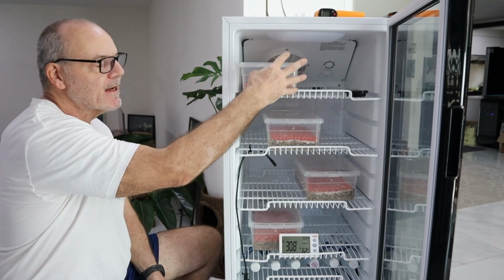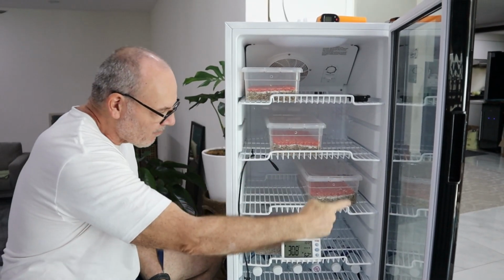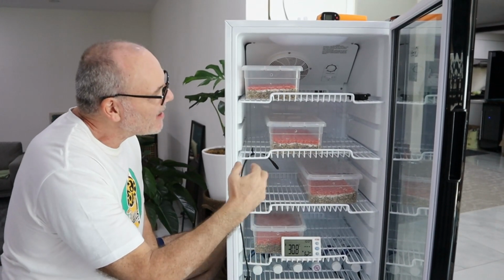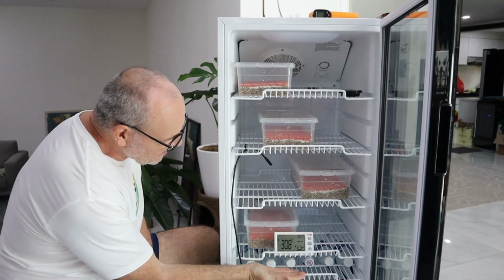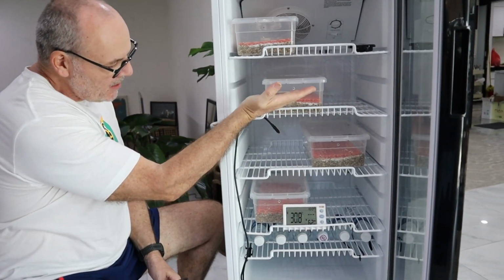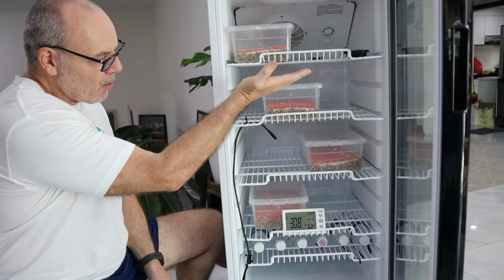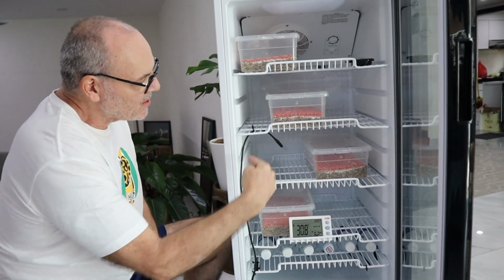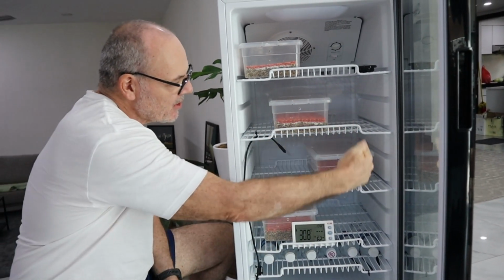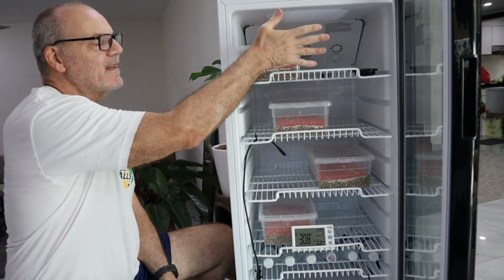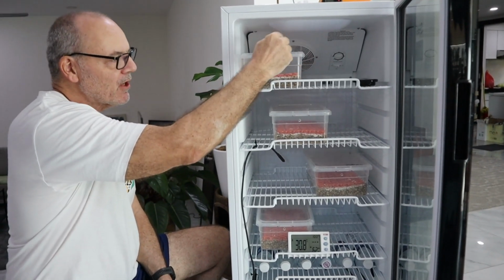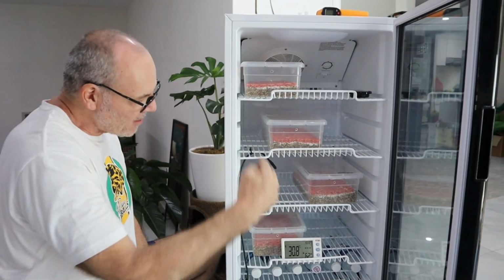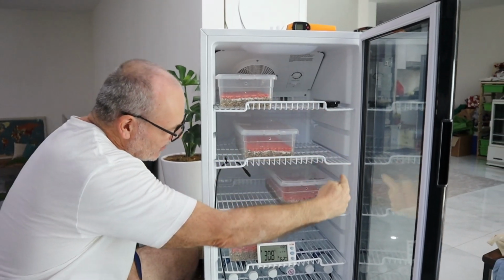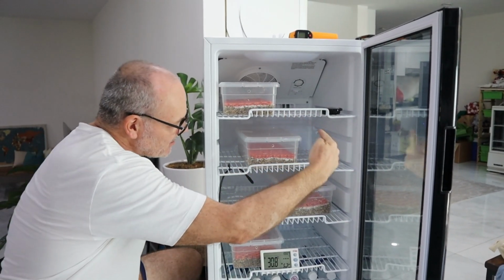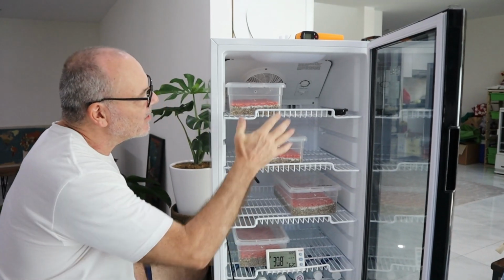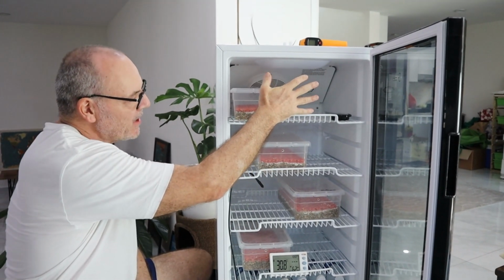The only way that the heat can get up to the top of the incubator is via convection currents, and I think what's happening here is that we're getting a nice bit of convection in the top two-thirds of the incubator, so we're getting some circulation here, but we've got a little bit of a dead zone at the top. It's a little bit cooler at the top, so the convection currents are not actually making it all the way to the top. They're actually circulating in this part of the incubator here, and we've got this dead zone here.